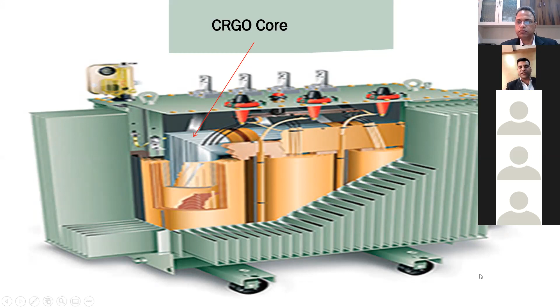In the next slide, I'm going to describe the CRGO process mapping. For CRGO process, the first and foremost thing is selection of the raw material. This process starts with the transformer manufacturer's designs - my customers are transformer manufacturers. They give their designs, and we need to select raw material that meets their technical requirements. The main technical requirement is the no load losses, so according to their no load loss requirement, the CRGO processor selects the CRGO grades. Selection of the right raw material is the main area in the processing part.